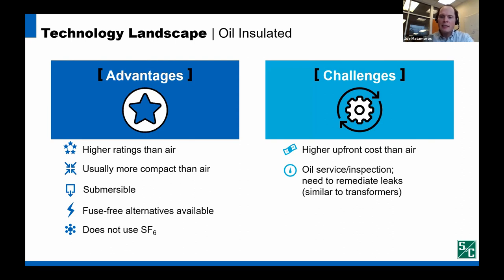This is a significant disadvantage to the other submersible technologies available. Oil needs to be regularly monitored and maintained. And as with a leaking distribution transformer, an oil leak of oil insulated gear would require some form of remediation or soil remediation. Lastly, oil insulated gear has a large carbon footprint due to its large mass and higher maintenance requirements.